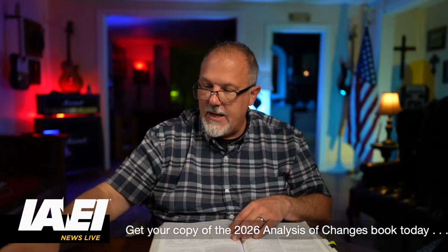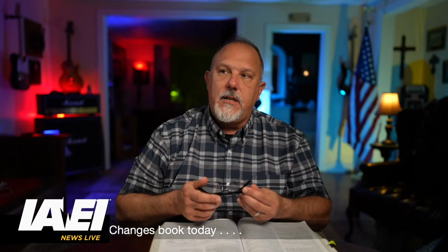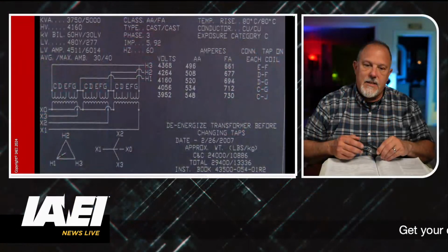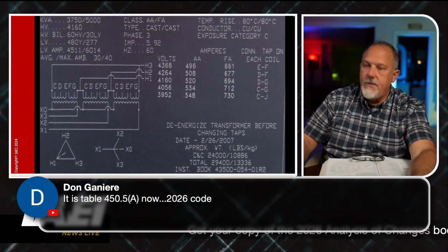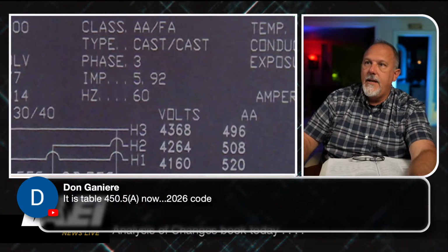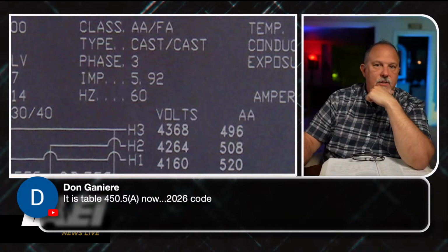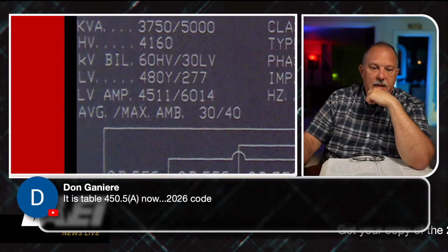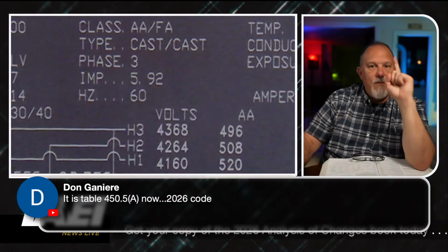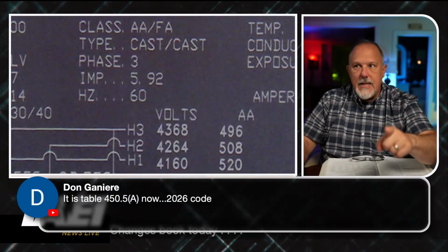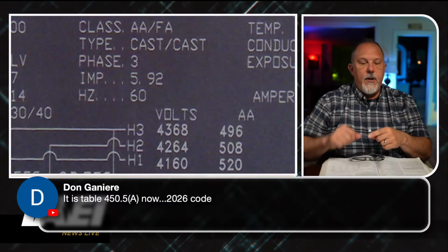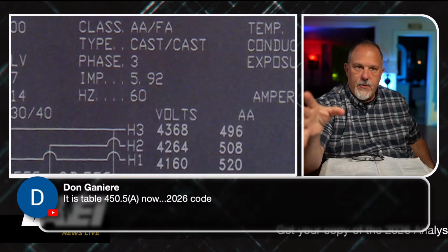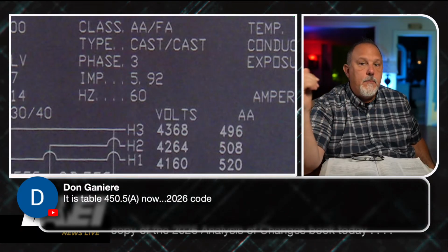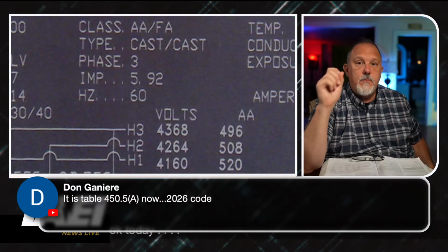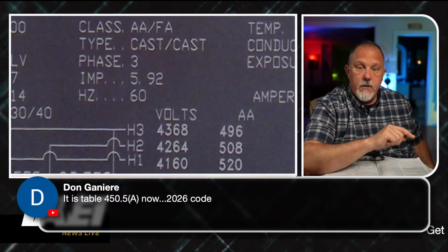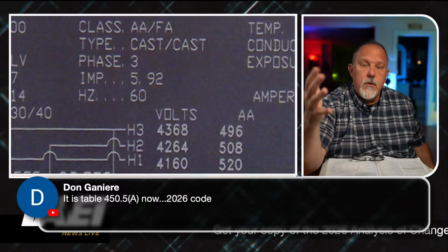But I had a really good question asked, and it was asked after we got into the discussion of the impedance. So if you look at this nameplate, I don't know if I can do this. Can I? Yes, I can. The impedance on this nameplate is 5.92, yet my kVA is 3750 and 5,000. Why do I only have one impedance? And the reason is because adding fans or not adding fans has no impact on the impedance of the transformer. The impedance of the transformer is based upon the physics and the construction of the equipment. So that would be the core and etc., right?